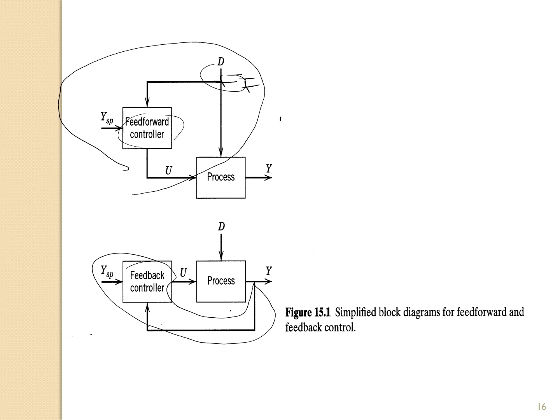Advantages and disadvantages of feedback and also feed forward. The feedback control loop's corrective action occurs as soon as the control variable deviates from the set point. The control variable is the same as the process output. So once the process output deviates from the set point, it will take the corrective action. Next, corrective action occurs regardless of the source and the type of disturbance. That means this corrective action is done without taking into consideration the type of disturbance or any other sources. The other advantages are that it requires little knowledge about the process, and it is also versatile and robust.